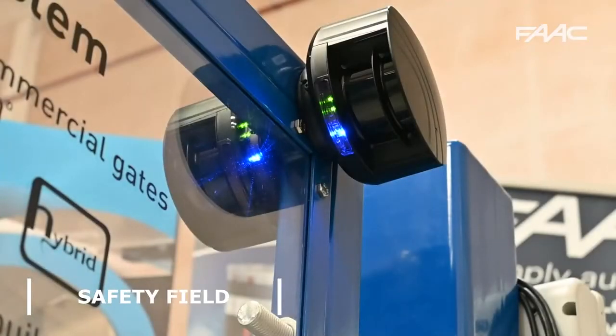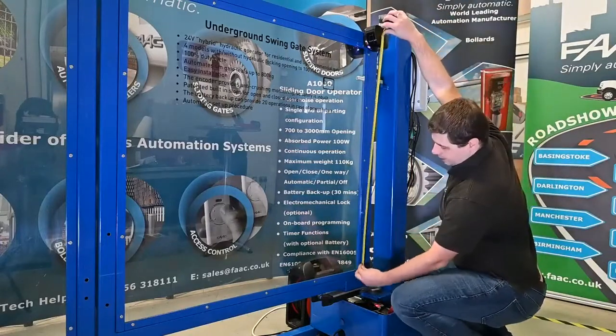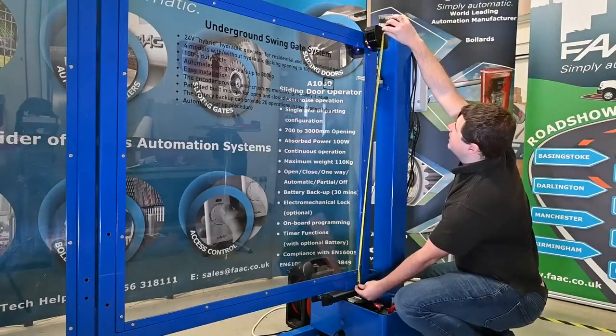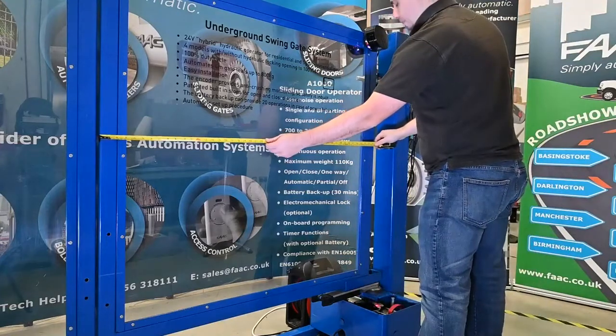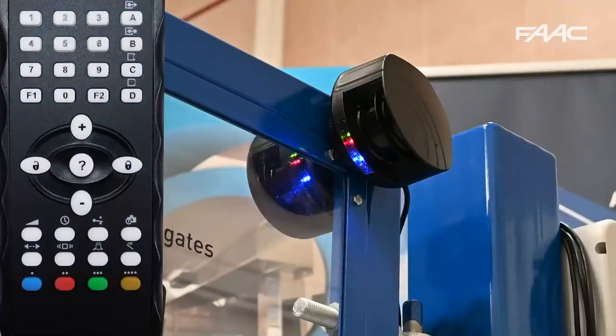The next stage is setting the safety field. First measure from the center of the X-guard down to the bottom of the gate, and also the width of the gate, as we'll need those figures to put into the safety field. So you unlock and do the height first — press D, so the light starts rapid flashing, then you enter the height. In this case 1.2, then it goes back to the slow blinking again.